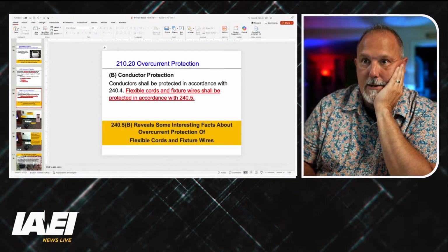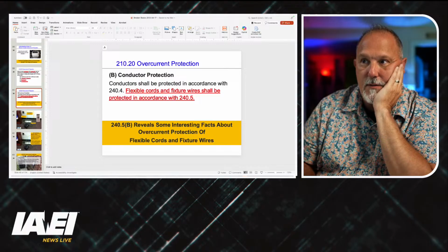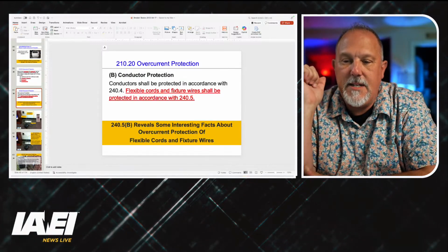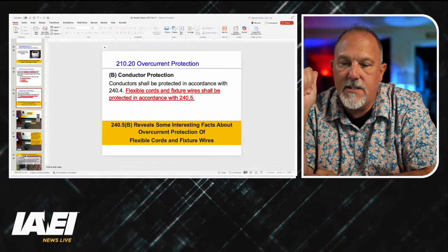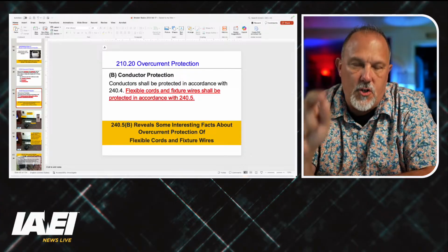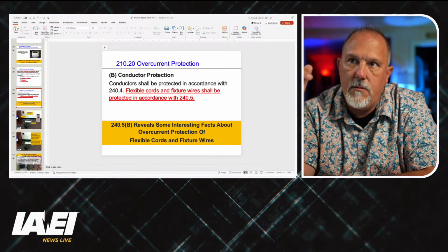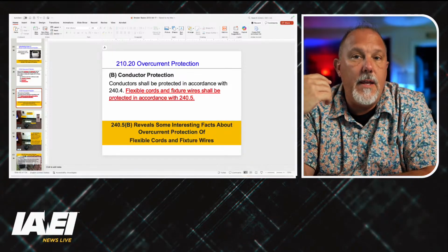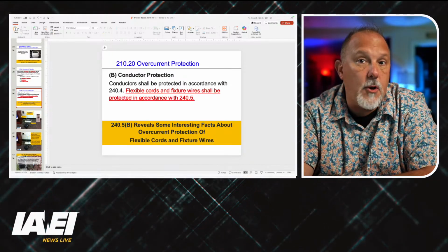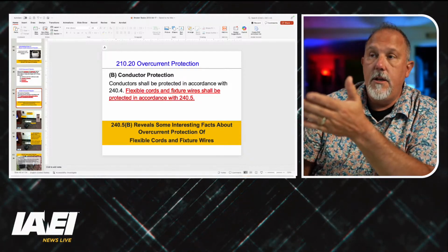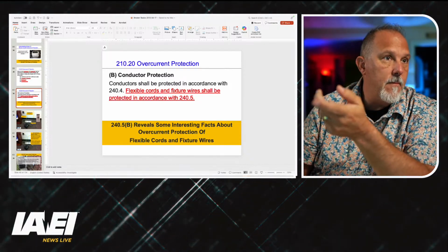I was talking about the attached conductors because, hey, happy Tech Tuesday. We got Willie Snyder in the house. I would get questions about the conductors of, say, a lamp cord or whatnot, and the proper overcurrent protection based upon Article 240, because actually 210.20, let's take a look.